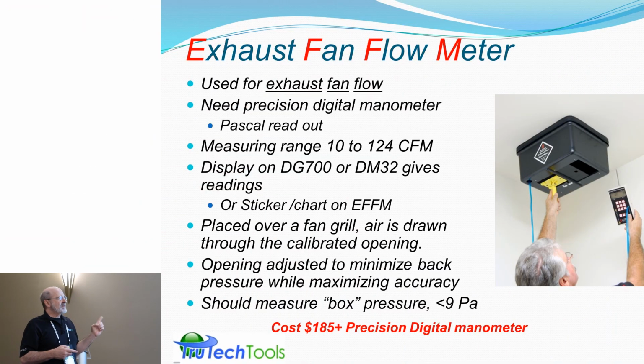Exhaust fan flow meter, basically it's a flow box. It's a box that has a calibrated door opening in it so that when return air is flowing through it within its range, it creates a negative pressure inside the box. And that pressure, if you know the square of the opening, it's called the open hole formula, you can actually determine what the airflow, the CFM, is.